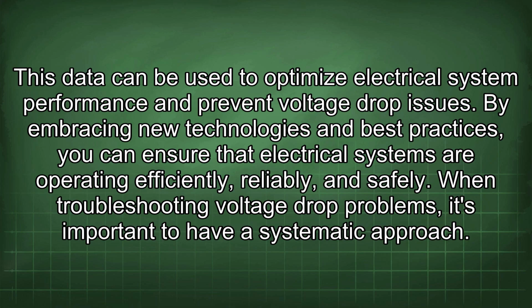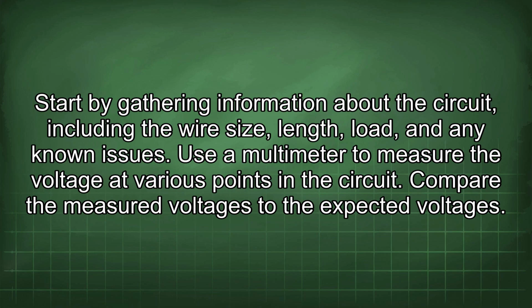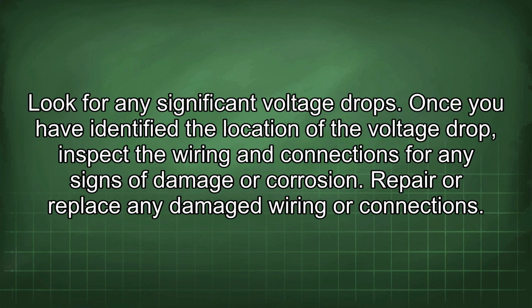When troubleshooting voltage drop problems, it's important to have a systematic approach. Start by gathering information about the circuit, including the wire size, length, load, and any known issues. Use a multimeter to measure the voltage at various points in the circuit. Compare the measured voltages to the expected voltages. Look for any significant voltage drops.